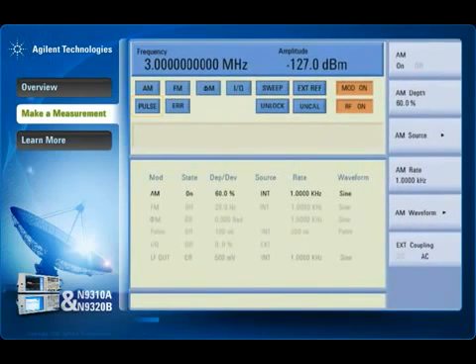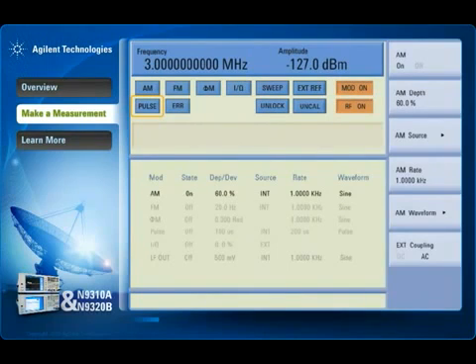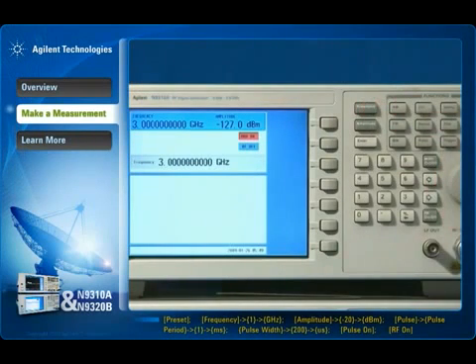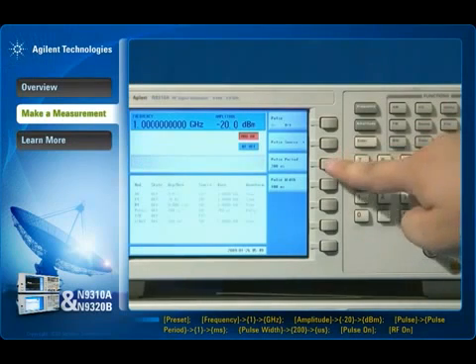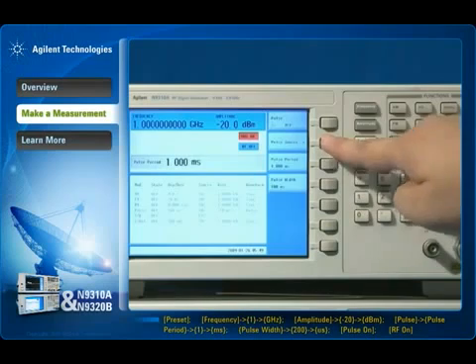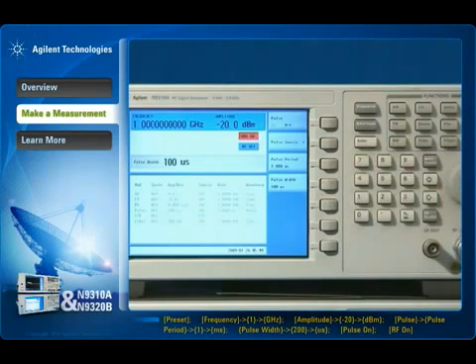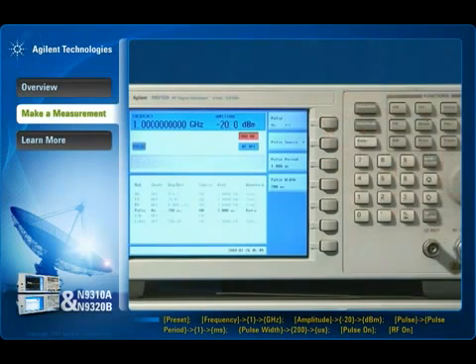This demonstration shows how you can easily configure the N9310A to generate a pulse modulation signal and set the pulse period from 200 microseconds to 2 seconds — for use in, for example, an EMC test or component test. To generate the pulse modulation signal, set the center frequency and amplitude of the signal generator. Then enter the pulse modulation mode and set the pulse period and pulse width. When you activate the pulse on and RF on, the pulse modulation signal is generated.